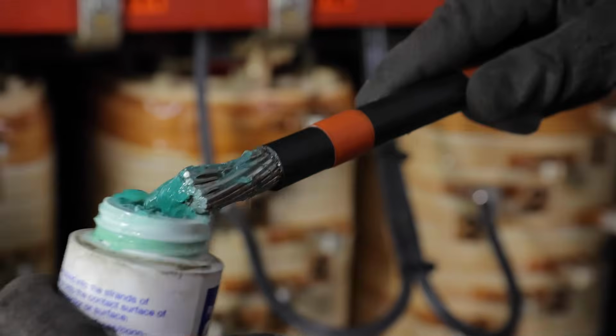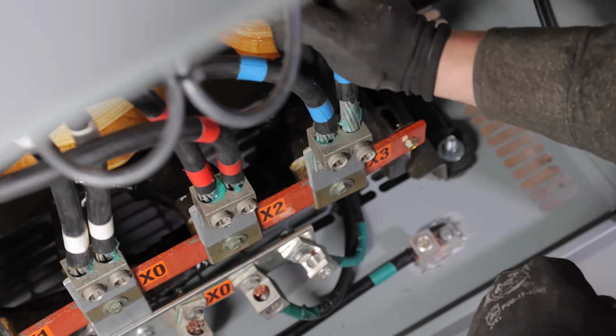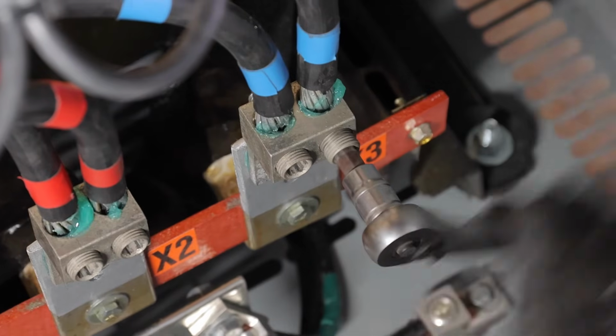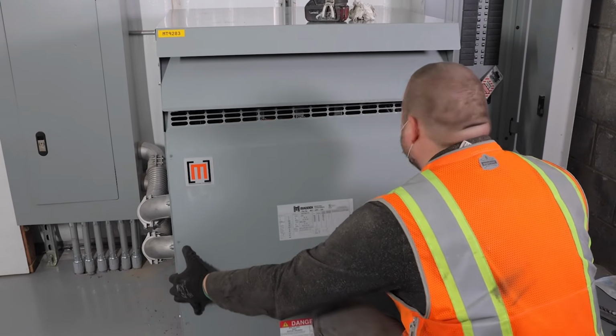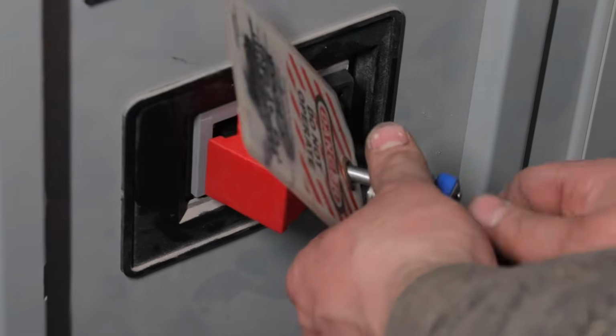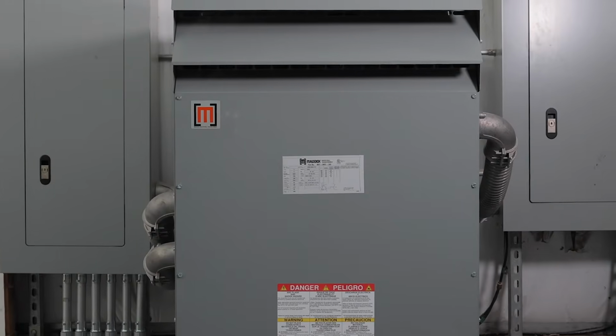The primary wires are connected to the primary lugs, and the secondary wires are connected to the secondary lugs. The front panel is then reinstalled. The lockout is removed from the breaker, and the transformer is energized.